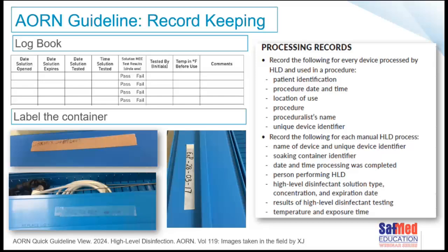Then, of course, do you have a logbook for all the devices that were actually done in this? So here the AORN talks to this, and a lot of us are used to having a logbook to record the fact that we tested the minimum efficacy of concentration, but very few people that I know of have got a logbook to document every time we soak something, because that's what we're supposed to do.